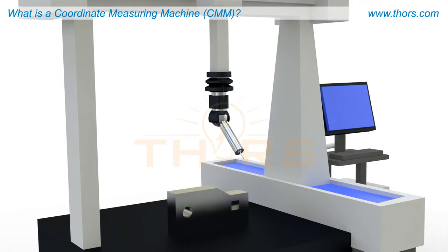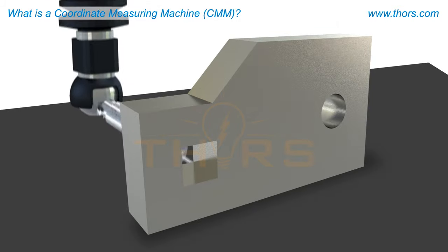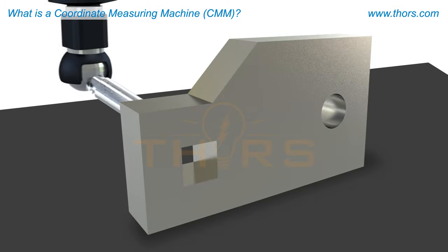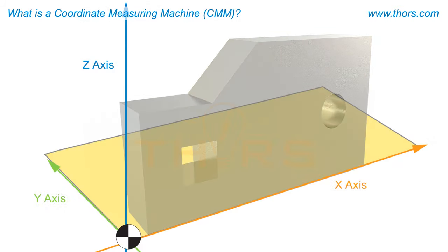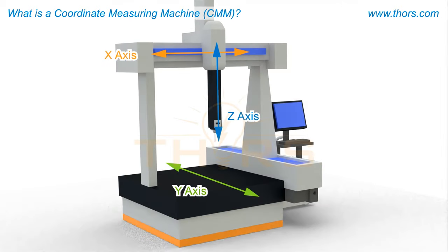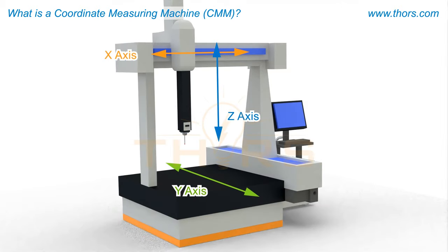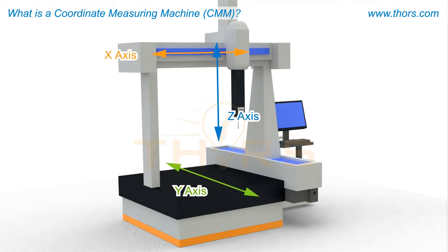A CMM measures the geometric features by acquiring the coordinates of points on the object's profile. The coordinates of points are a set of three values that determine a point's location relative to a defined origin in a three-dimensional space. These are acquired by a mechanical system which moves a probe along the X, Y, and Z axes.